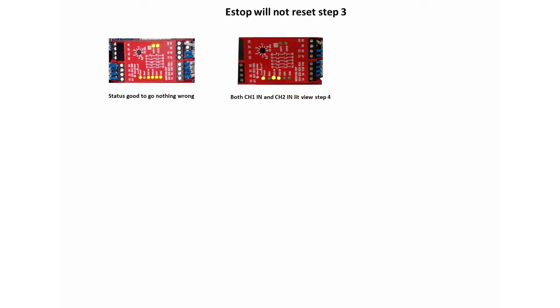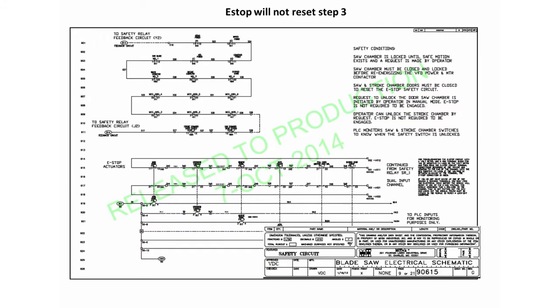If one or both of the LEDs are not lit, it will be necessary to check the voltage. To check the voltage, locate circuits CH1 IN and CH2 IN on the electrical schematic page 9, drawing 90615.